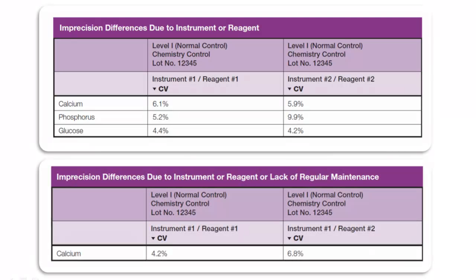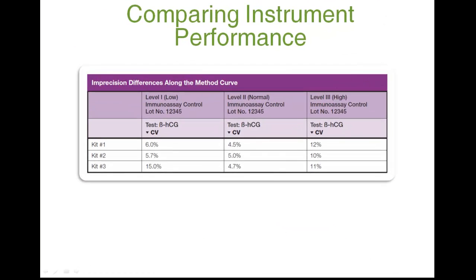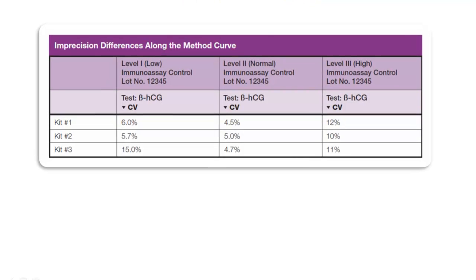In the second table, the difference in performance is probably due to the change from reagent 1 to reagent 2. However, it could also be due to lack of regular maintenance or some other cause. The data in this table is for three different kits for testing beta-HCG. Kits 1, 2, and 3 exhibit similar performance in the normal range and at the high end of the method curve. However, kit 3 has a much higher CV at the low end of the curve, providing justification to use either kit 1 or 2 rather than kit 3 for testing.